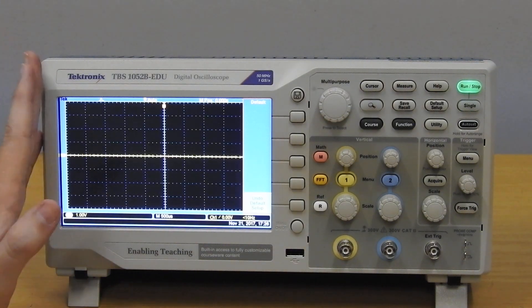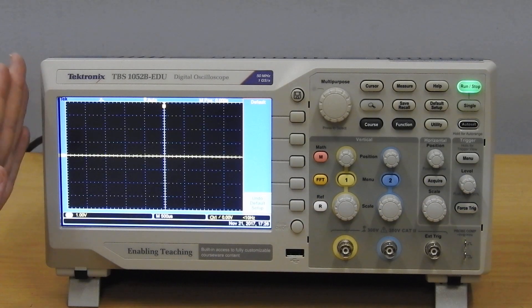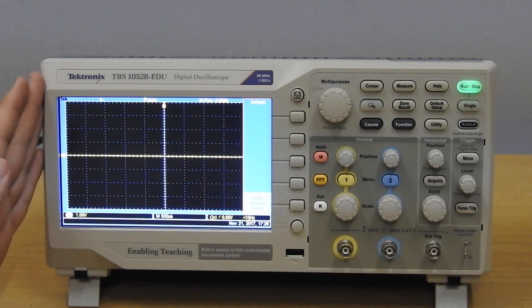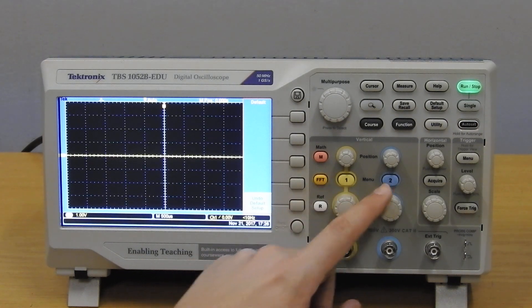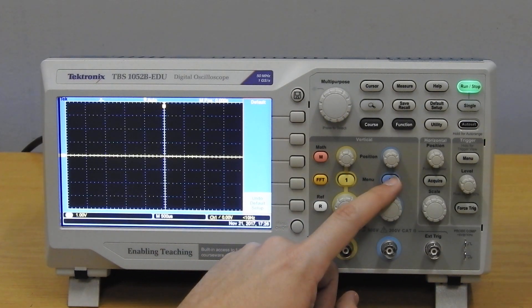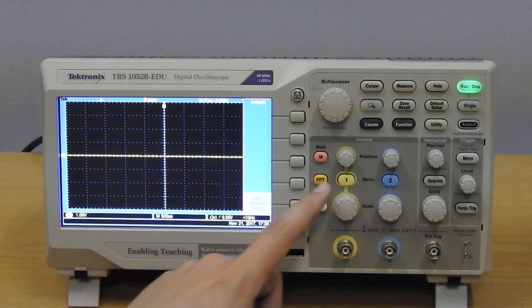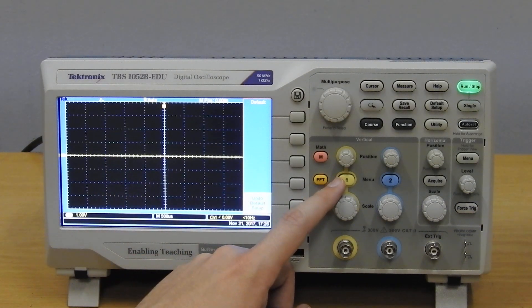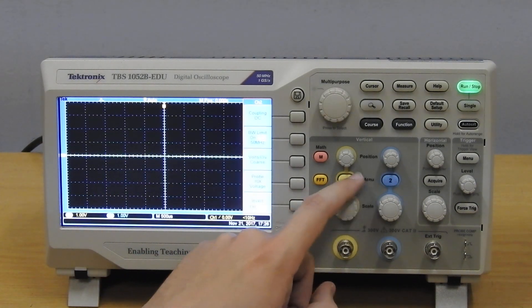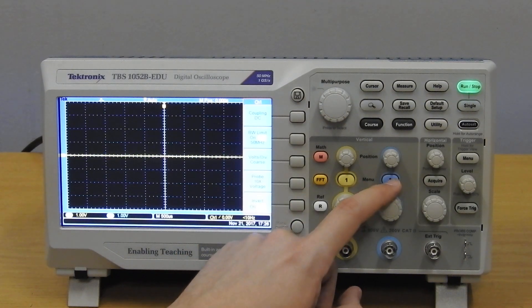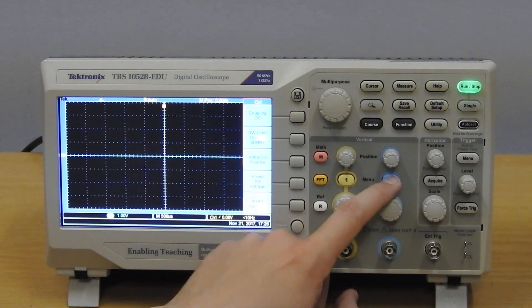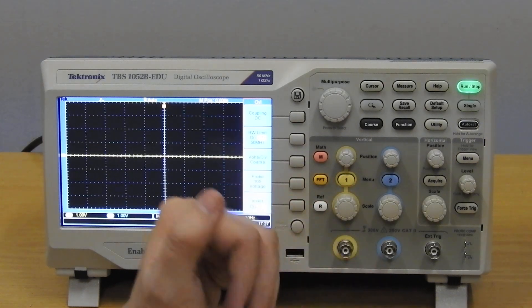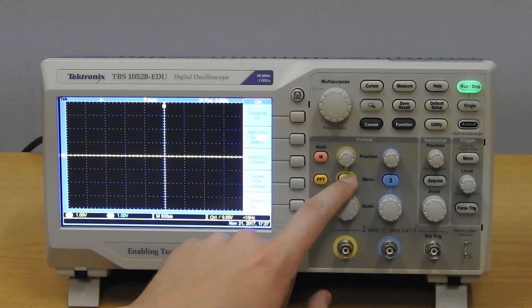Now as I said in the beginning, this scope is designed to work with times 10 probes and you are going to use times one probes. Every channel you can control individually. The yellow signal is connected to the yellow button and the blue signal is connected to the blue button. So pressing one of these buttons will bring up the menu for that channel.